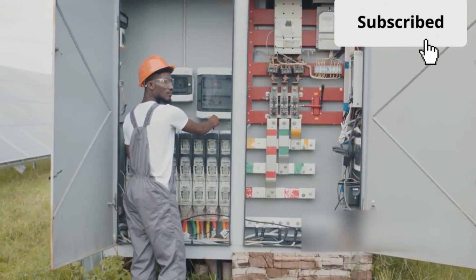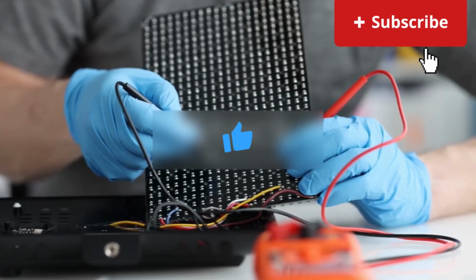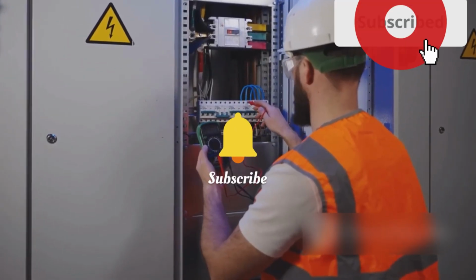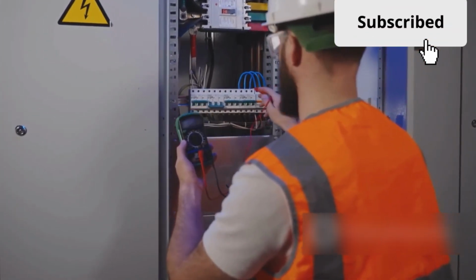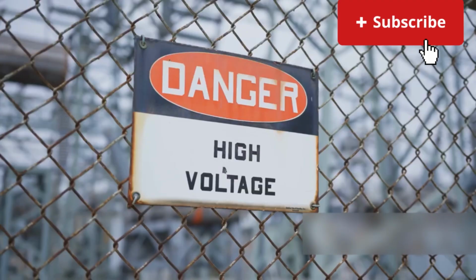Over time, the contacts can wear down due to the arcing that occurs during operation. Inspectors use specialized tools to measure the contact wear and determine if they need to be replaced. It's important to remember that maintenance should only be performed by qualified personnel who have the necessary training and experience to work with high-voltage equipment. Safety should always be the top priority.